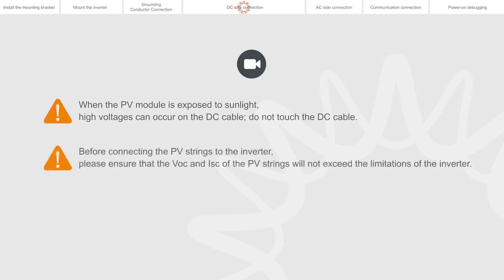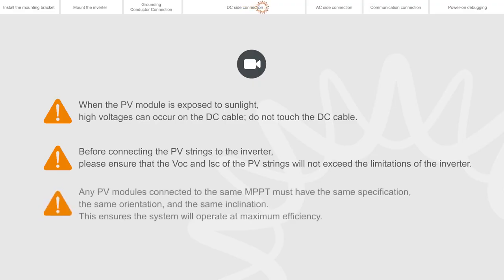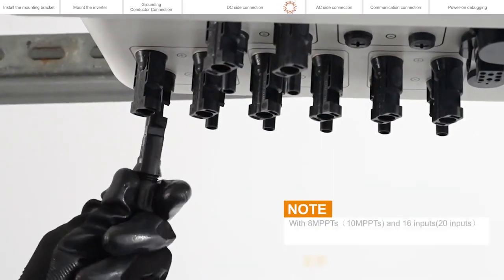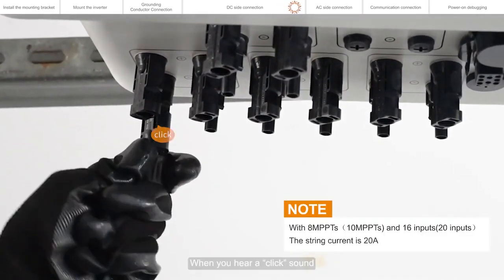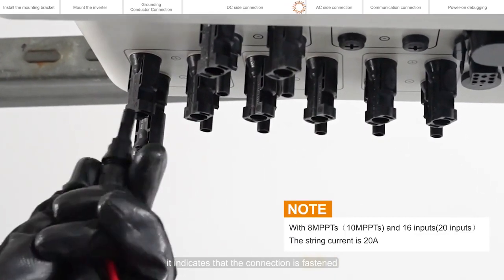Before connecting the PV strings to the inverter, please ensure that the VOC and ISC of the PV strings will not exceed the limitations of the inverter. Any PV modules connected to the same MPPT must have the same specification, the same orientation, and the same inclination. This ensures the system will operate at maximum efficiency. When you hear a click sound, it indicates that the connection is fastened.